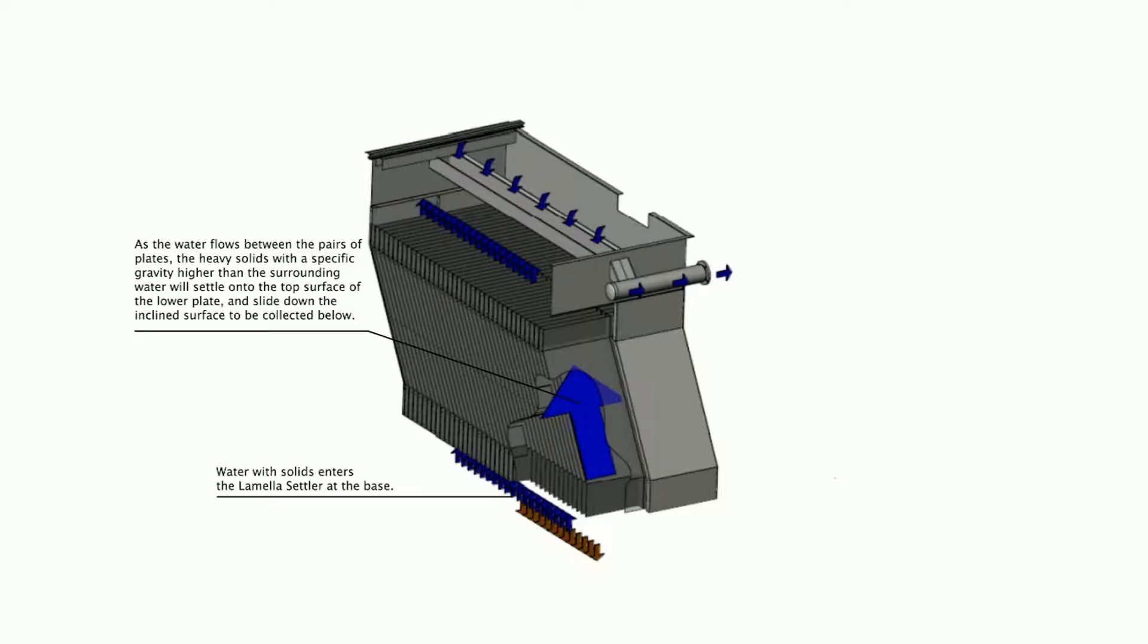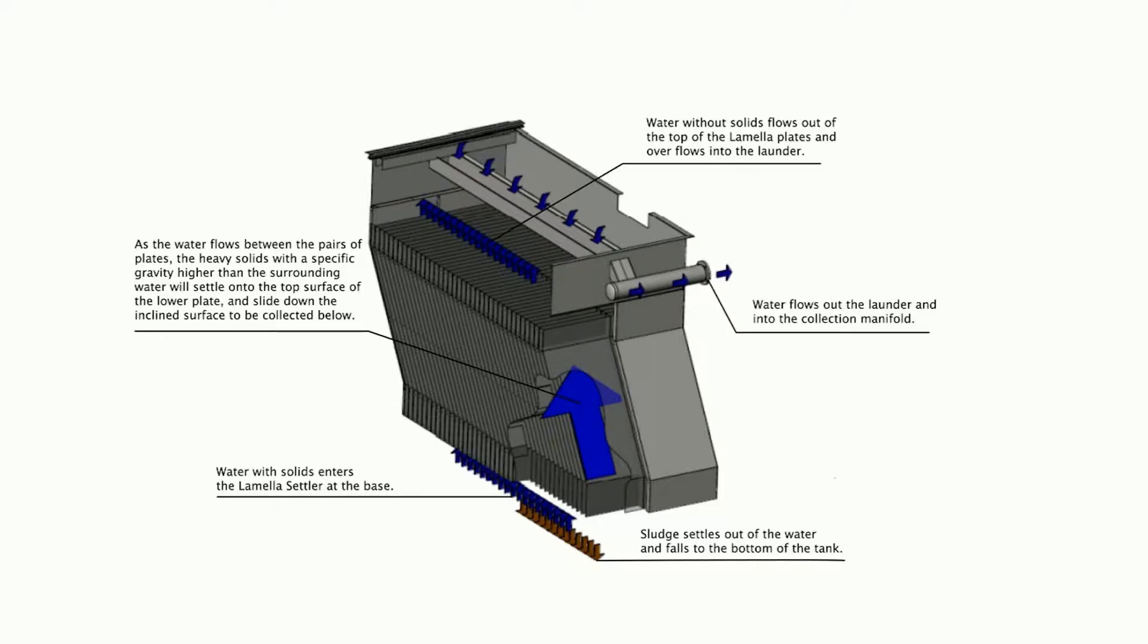As the water flows between pairs of plates, the heavy solids with a specific gravity higher than the surrounding water will settle onto the top surface of the lower plate and slide down the inclined surface to be collected in the sludge hopper. Clear, nearly solid-free water then exits the top of the plate area and flows over an adjustable weir.